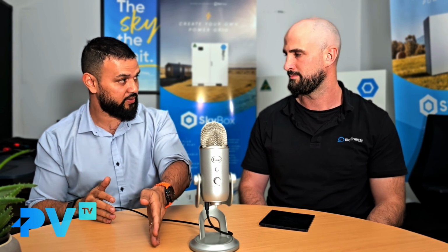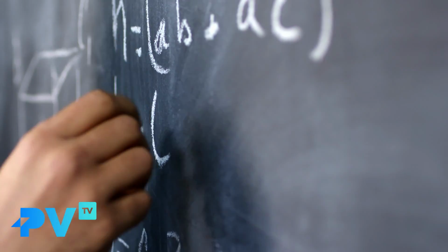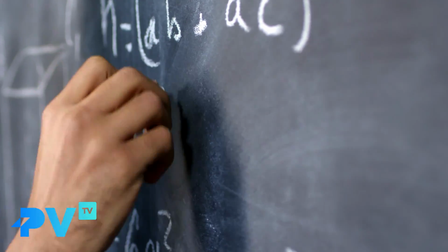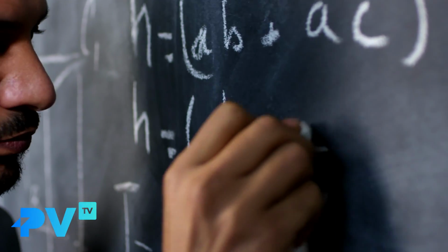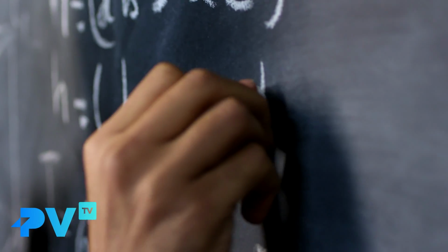What's the alternative to that? What if you don't have the BMS? Well, how it works is you tell the inverter, I've got a 10 kilowatt hour battery. The inverter starts doing maths, going: okay, if you're consuming 1 kilowatt for 3 hours, you must have used 3 kilowatt hours, so therefore the battery must be 70%. It's a guess. There's a lot of algorithms and maths going on, and different inverters, Victron, SMA, Selectronic, do a pretty reasonable job at getting that state of charge estimate.